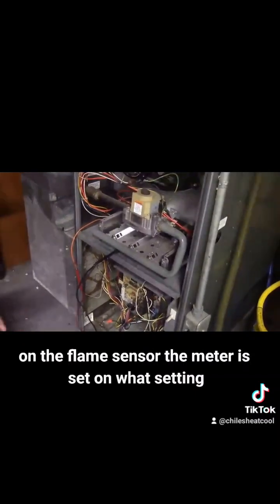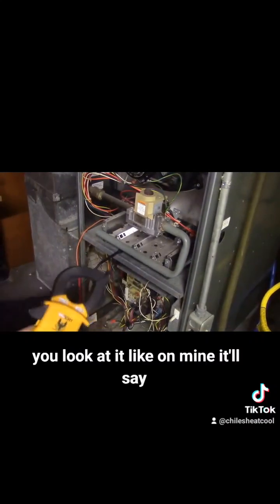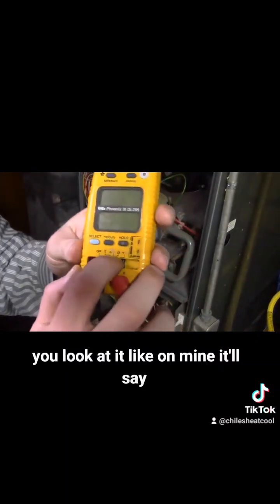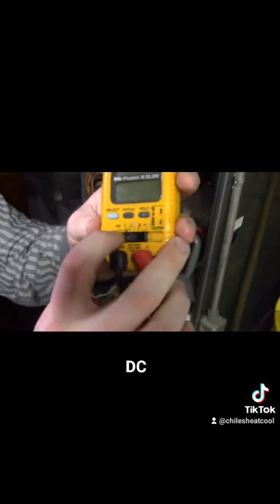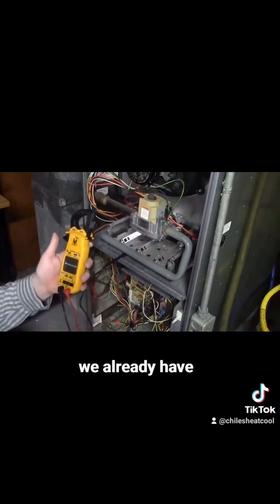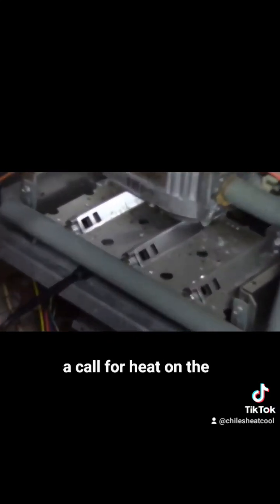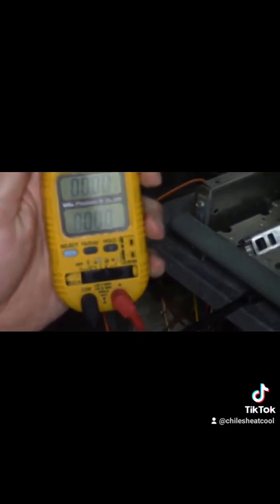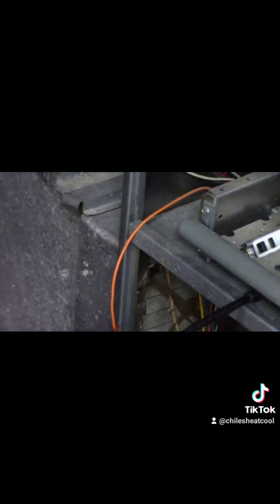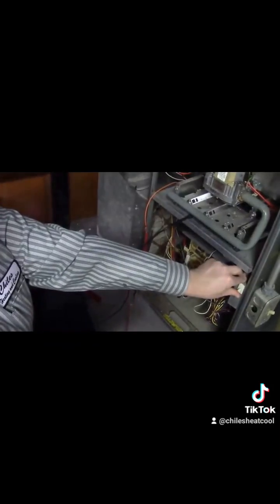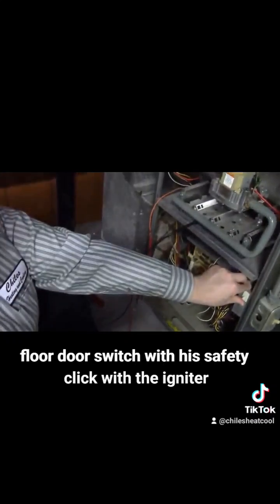The meter is set on what setting? That's right, microamps DC. When you look at it, like on mine, it'll say UA DC, microamps DC. We already have a call for heat on the thermostat, just like this. So we're going to fire it up. Just have to remember to hit the door switch. That's found on here, right there. Blower door switch, which is a safety. Click with the igniter.